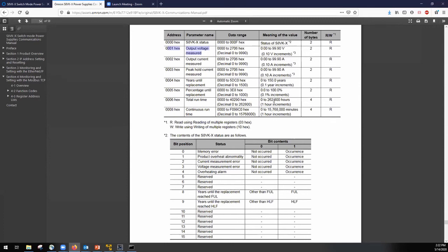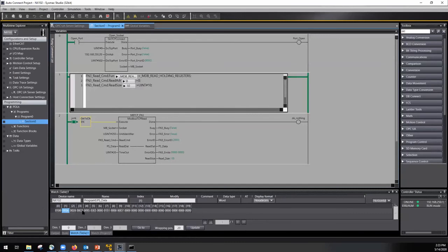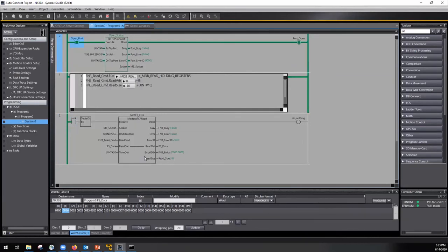That being said, to put Modbus into a piece of equipment is a lot cheaper, which is why you typically see run-of-the-mill equipment all Modbus capable, whereas with EtherCAT you have to have the EtherCAT chipset. You essentially have to pay it back off every time you implement EtherCAT into anything, so it makes stuff a little bit more complicated. However, when you go with EtherCAT, the benefits are well worth the money, I think, especially in just initial setup.